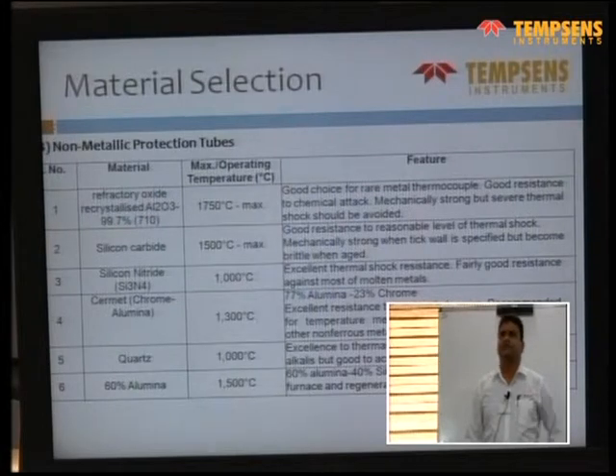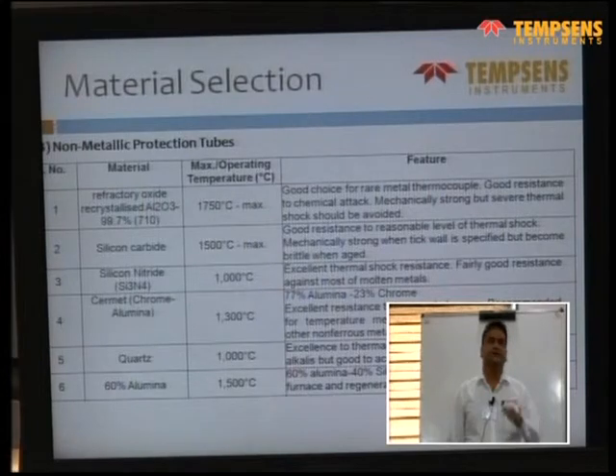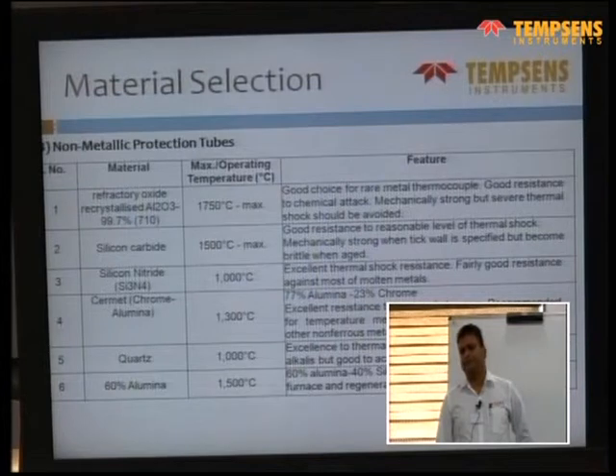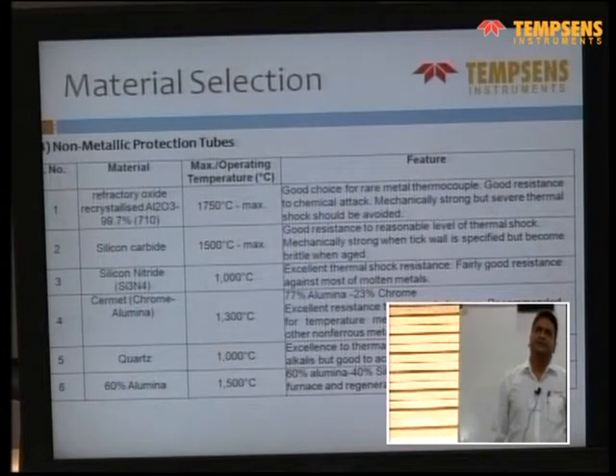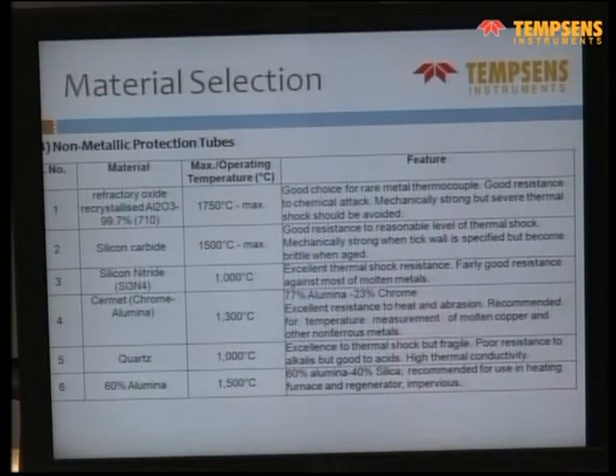Then silicon carbide, it has good temperature resistance up to 1500 and good thermal shock resistance. So this is also used in combination, where inside can be an alumina tube and outside can be a silicon carbide tube for better thermal shock resistance. Then silicon nitride or Sialon, this is used for molten aluminum application, and this tube is non-wetting with molten aluminum. Then Cermet is again for high temperature. It is a metal ceramic, and it has 77% alumina and 23% chrome. This is used for molten brass application, or even for molten copper application.